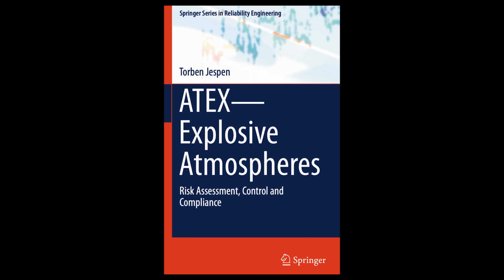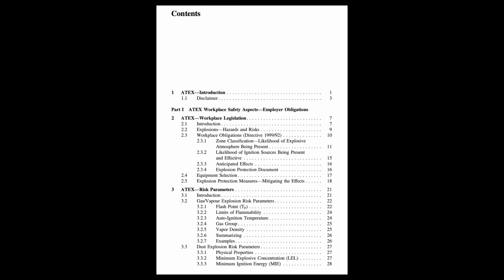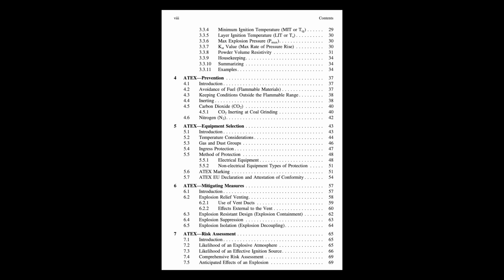Now, what about dusts? The guide highlights some key differences when dealing with explosive dusts. Yes, dust explosions have their own distinct characteristics and parameters. The very first step, actually, is determining if the dust is combustible at all. There are standard tests that classify dusts into Group A, combustible, or Group B, may burn, but doesn't readily propagate flame. So first, can it even explode?